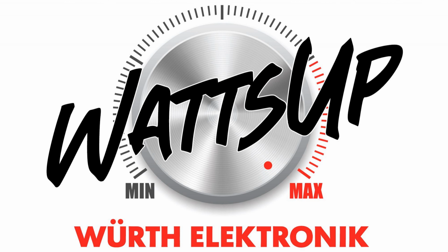The final parameter is this epsilon r. We can also reduce this by using very low dielectric varnishes, or in the case of potted transformers, potting compounds, or even better, having no varnish or potting compound, and then we get our epsilon r down to 1, which is as low as it can go.